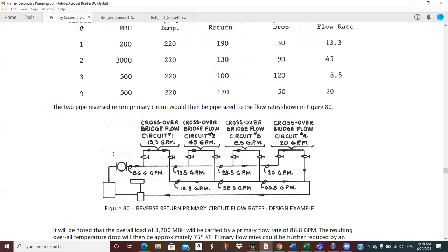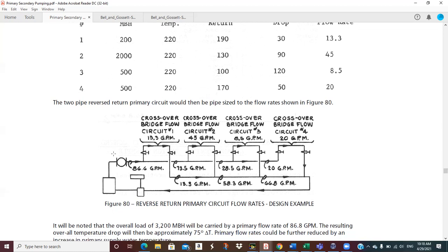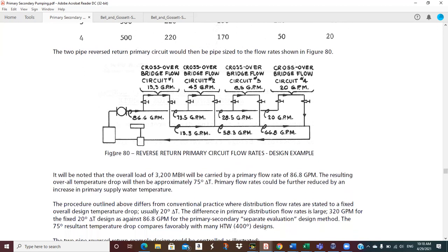And it's right about, I get about 74, but he used the wrong number. So he got 75. Anyway, so we get a delta T of about 75. So if we're 220 out minus 75, we're going to be about 145 degree water temperature back to the boiler. Okay, so that's pretty simple. So that's how you can size your crossover flow rates. If you got questions, you can jump in there.